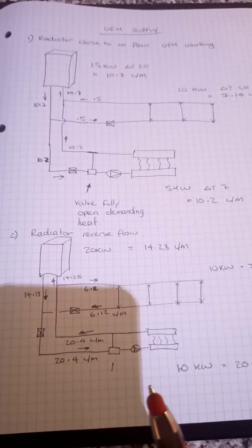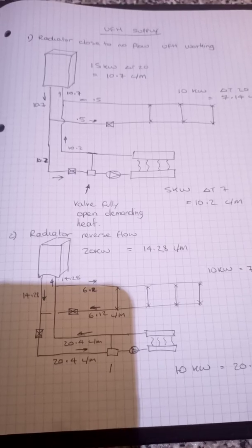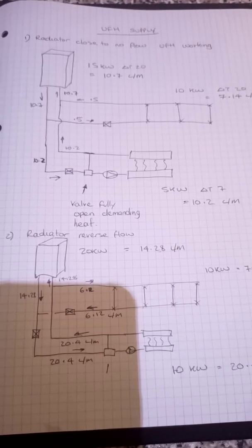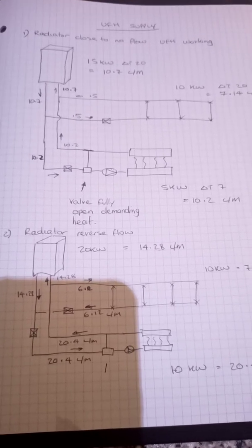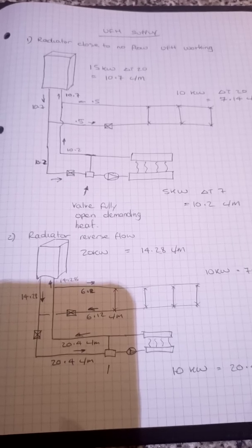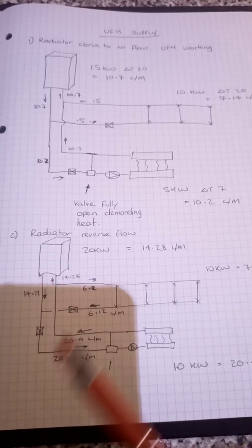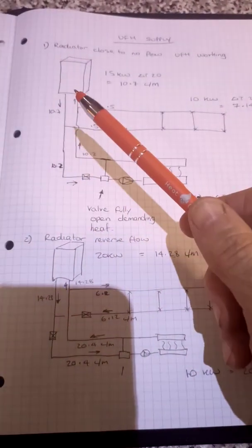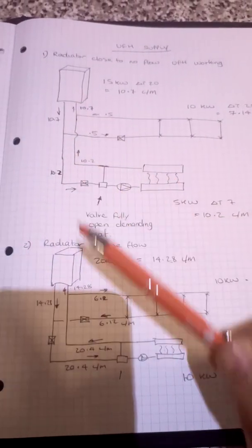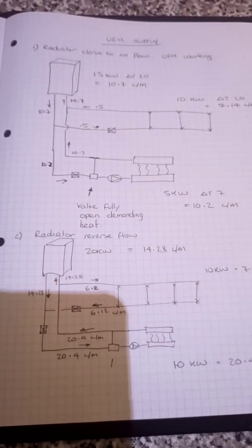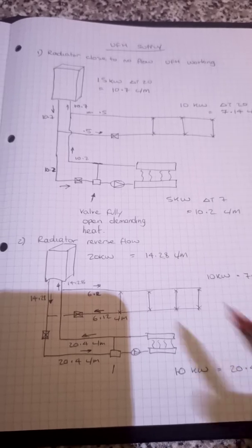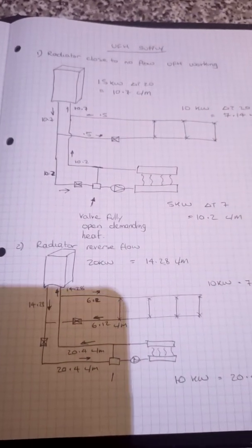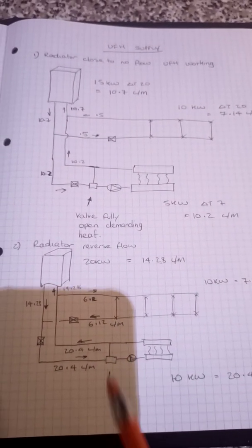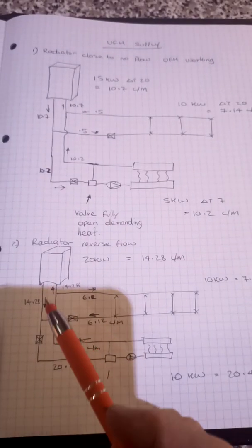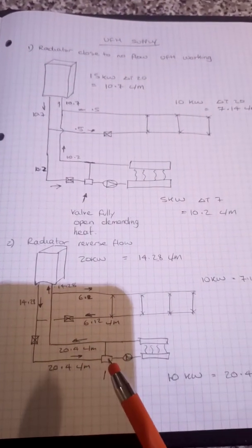Now the other reason is modern controls. So now we're fitting OpenTherm controls, weather compensation, TPI, and similar systems. These are deliberately designed to reduce the flow temperature from the boiler in order to reduce the output from the emitter and in order to promote more condensing efficiency from the modern boilers. And this leads to exactly the scenario. We've got a low temperature supply. We've got a valve here.